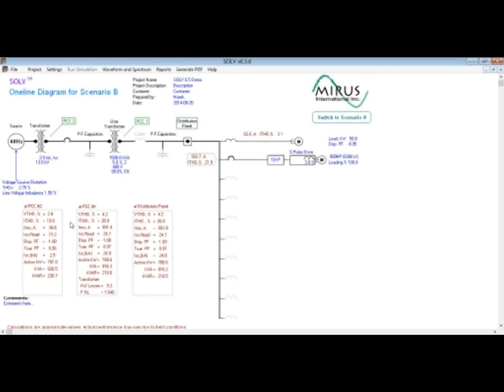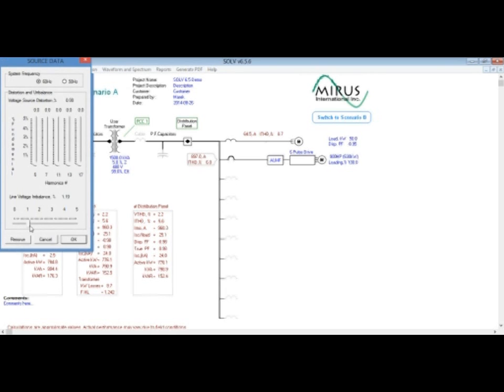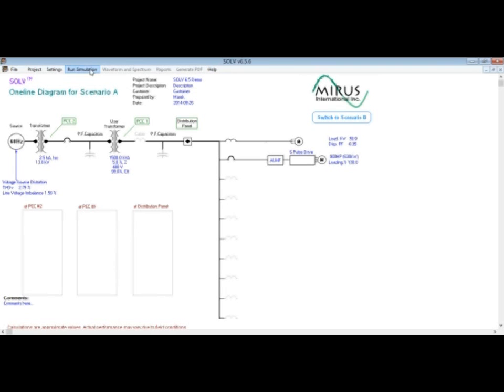Okay, so now we see that the performance dropped off even further with the 18-pulse solution. To compare this against the lineator under the pre-existing conditions, we can switch back to scenario A. So I click the switch to scenario A button to go back, and I apply the same source conditions as in the previous scenario. So 1.5% voltage imbalance, 2% of the fifth, 1.5% for the 7th, and so on, 0.5 and 0.2.